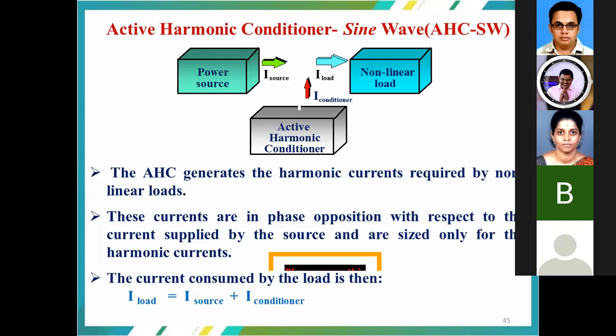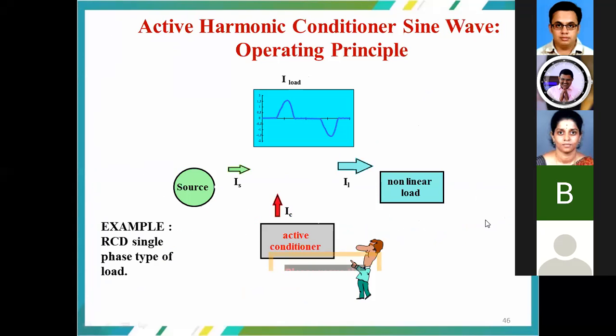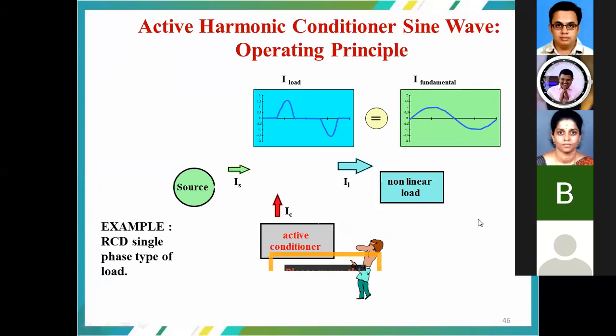The active harmonic conditioner is as shown in the figure. So the power source is going to be there, which is going to feed the nonlinear load, and this active harmonic conditioner is going to inject the I conditioner current, which is just opposite to the effect created by the nonlinear load. And the pictorial representation is as shown.